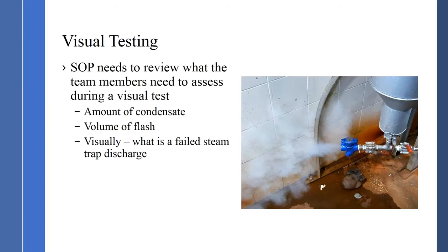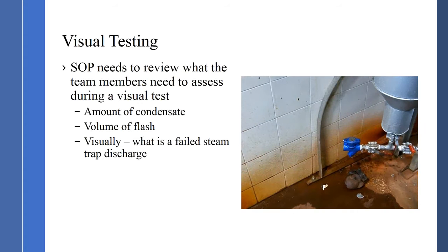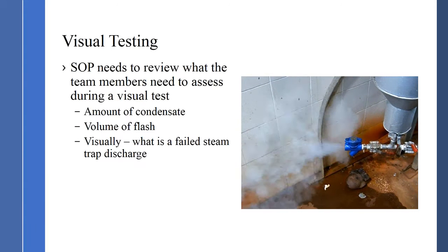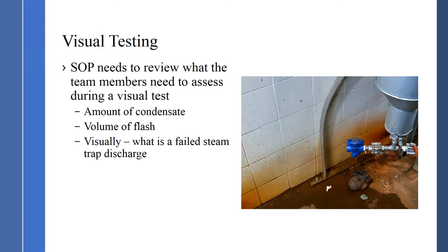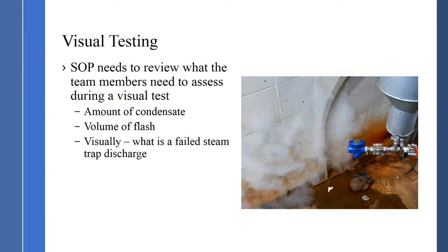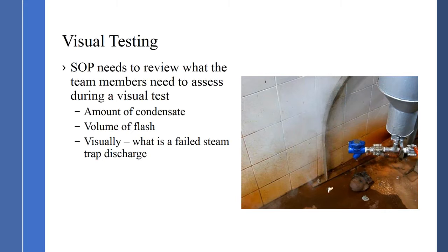Visual testing also checks whether the discharge is open to atmosphere — if so, you can visually see if the steam trap is working properly. Team members need to understand that at higher pressures, more flash steam is generated. The key is understanding whether the steam trap is discharging flash steam or blowing live steam through during its cycle process. It takes experience, but the more you do it, the more proficient you get. Visually, if the steam trap is blowing through completely, everyone can tell that; distinguishing flash steam from live steam leakage requires more training.